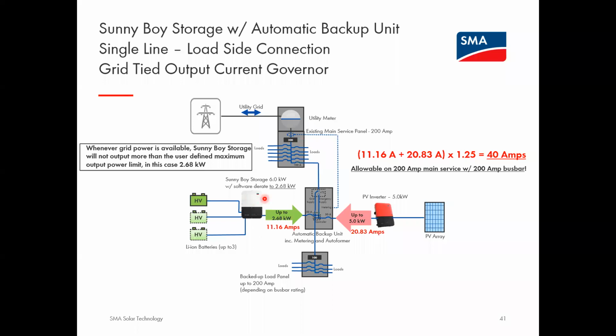Now, for most grid-tied use cases, 2.68 kilowatts is plenty of power. For example, with time of use, typically your time of use peak periods last 3, 4, 5 hours, and you don't have to discharge the battery all in the first hour. The financial benefit is the same if you discharge that battery slowly over the entire time of use peak window. And in doing so, it's actually a happier, healthier state for the battery. Discharging it slower helps extend the capacity and lifetime of the battery for your daily cycling use cases.